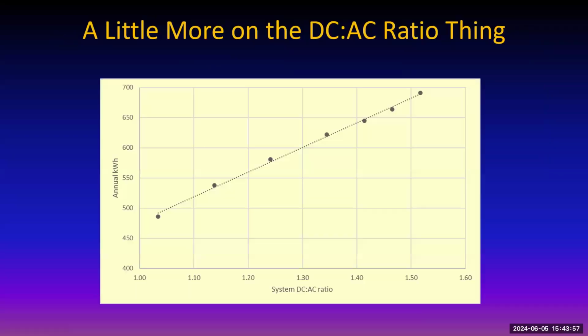We've talked about DC to AC ratio. Here's a curve showing that indeed with a DC to AC ratio of 1.5, you're still essentially getting out the rated power rating, the annual kilowatt hours. This is a simulation for different DC to AC ratios. And that's one of the things you enter into the simulation. And so that's why you'll see this a lot. And you'd see, gee whiz, I've got a 7,600 watt inverter and a 10,000 watt array. What am I going to do with that extra 2,400 watts? Well, the answer is they're probably not going to be there in the first place. And even if they were, it wouldn't be much over 7,600 watts, and it wouldn't be over for very long. And the inverter simply blocks it and says, no, we're going to stop here and wait till the sun gets a little darker or something.